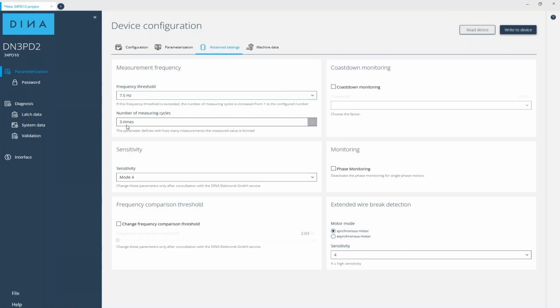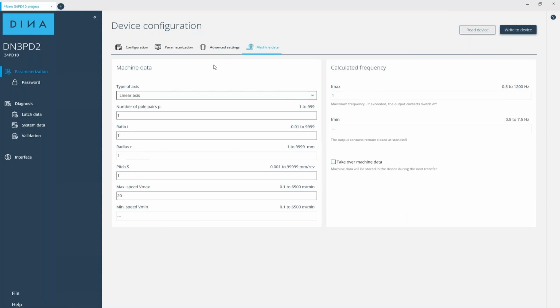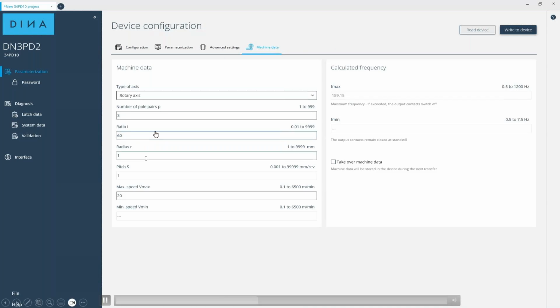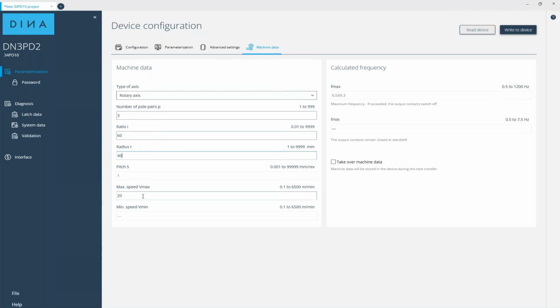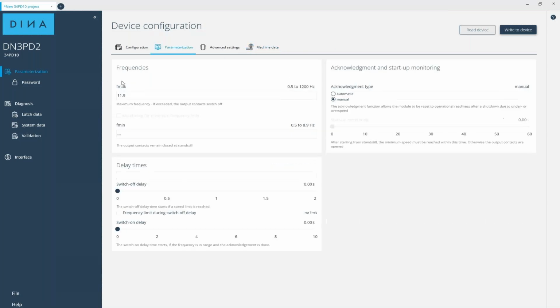In the advanced settings tab, you can perform fine-tuning. You can adjust how often the modules measure the frequency signal in a cycle, or set another sensitivity. You can activate phase monitoring or modify the extended wire break detection. These settings ensure very accurate safety checks. The tab machine data offer other function or options to set. You can set the physical drive parameters like axis type, number of motor poles, and gear ratios. The software then automatically calculates the necessary conversion, turning the mechanical limits, the speed, into the corresponding electrical frequency thresholds. This simplifies configuration by eliminating the need for manual calculation before applying the safety limits in the parameterization tab.